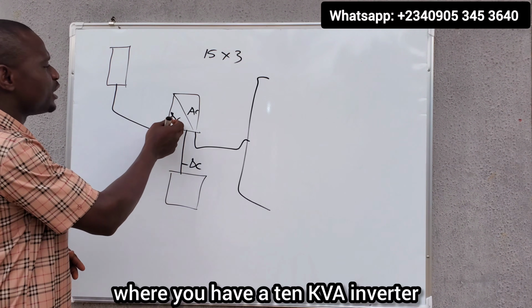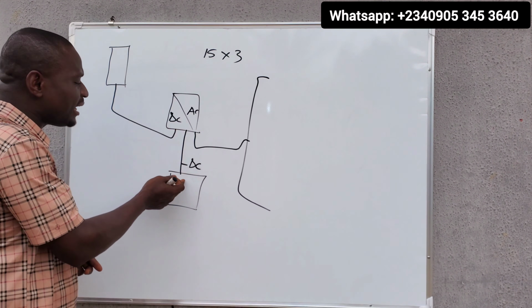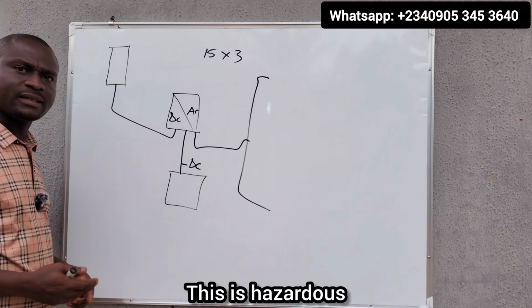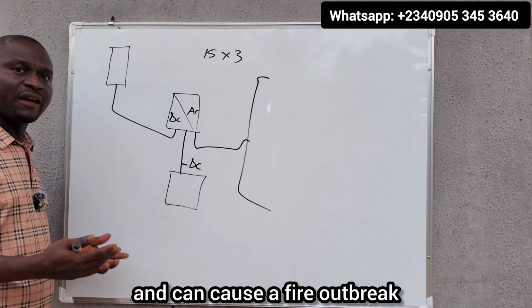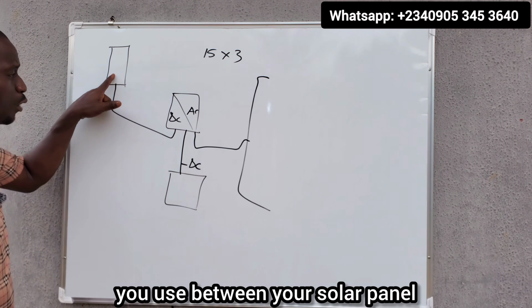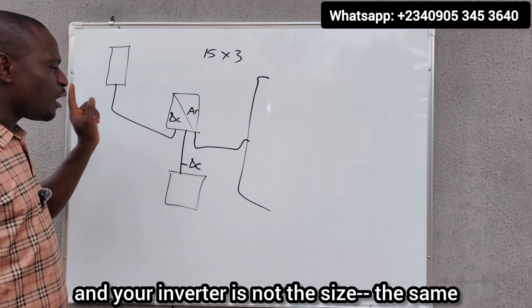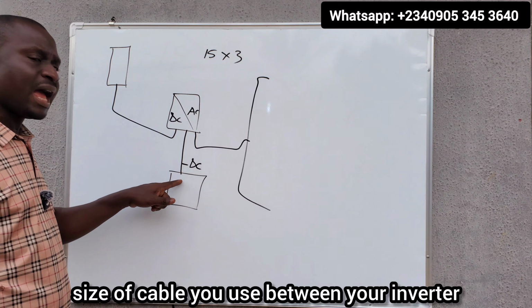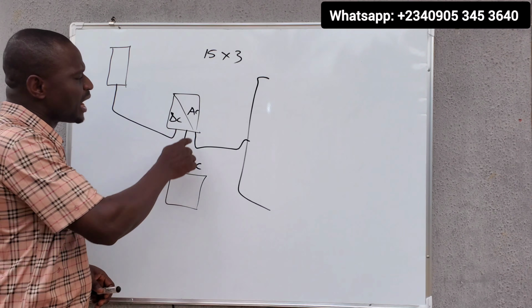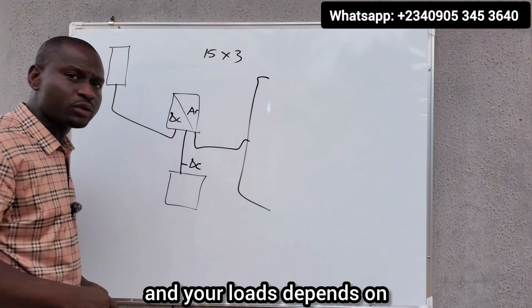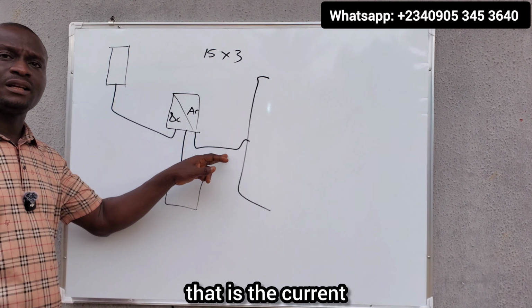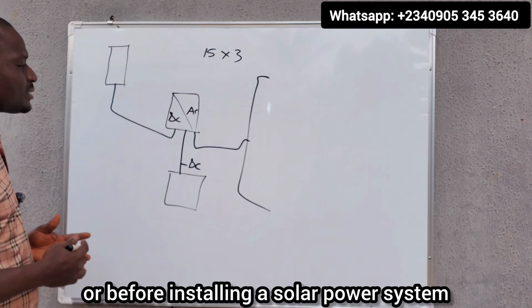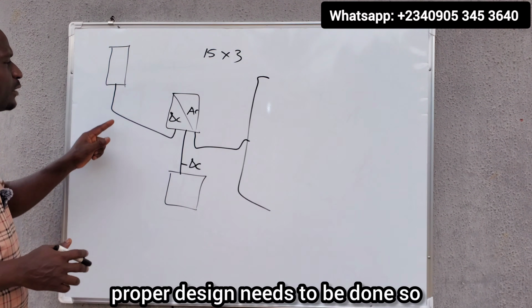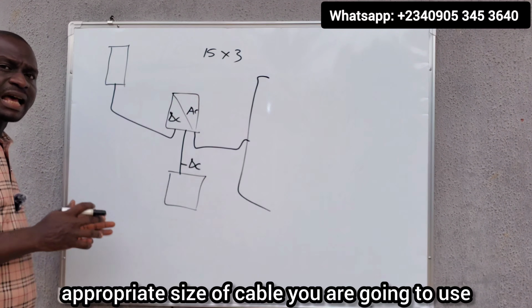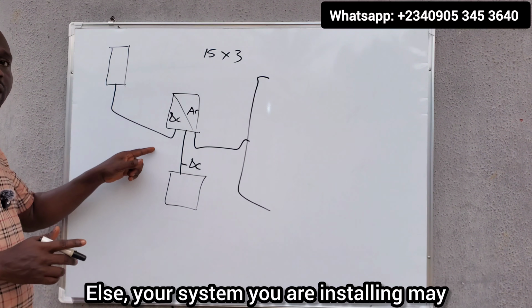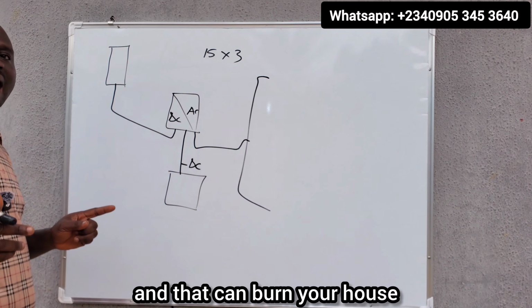You see situations where you have a 10 kVA inverter or a 10 kilowatt inverter and the installer will make use of 10 mm cable. This is hazardous. It is dangerous and can cause a fire outbreak. The size of cable you use between your solar panel and your inverter is not the same size of cable you use between your inverter and the battery, mostly for low voltage systems. The size of cable you use between your inverter and your loads depends on what will be flowing through them, that is the current. So when installing or before installing the solar power system, proper design needs to be done so that from there you know the appropriate size of cable you are going to use. Else, the system you are installing may pose a serious danger and that can burn your house.